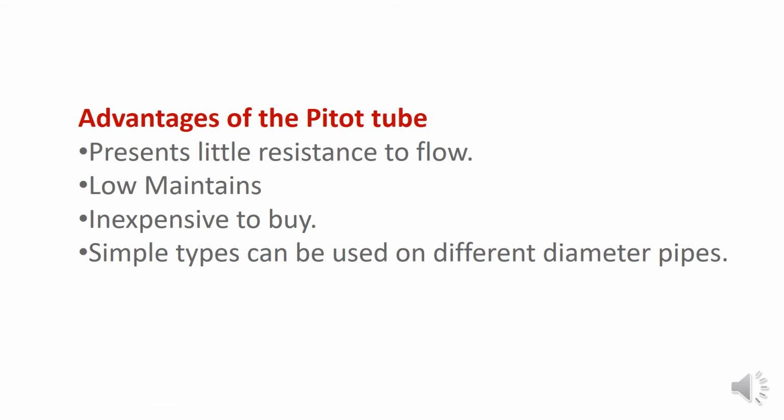Advantages of the pitot tube. As we saw in the image, there is no moving part in the pitot tube, so maintenance is very low. Also it is simple, so it is inexpensive to buy, meaning the cost of the pitot tube is very low. Also it presents very little resistance to the flow, because we are inserting a very small diameter pipe inside the fluid stream. Also we can use the same pitot tube in different diameter pipes.